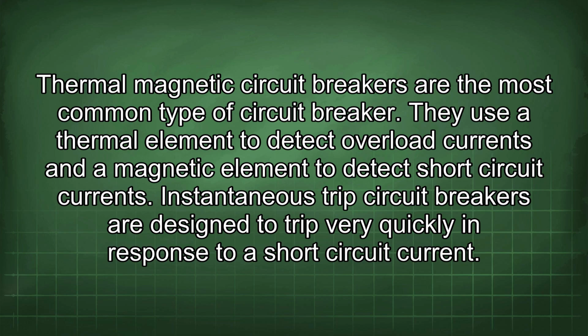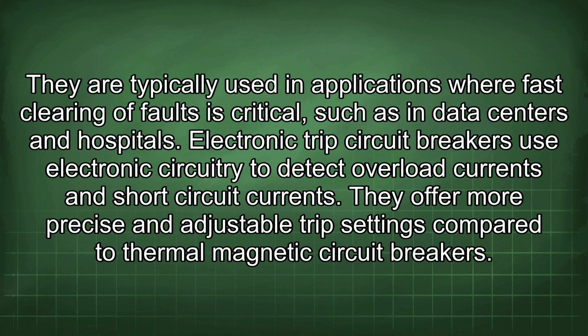Instantaneous trip circuit breakers are designed to trip very quickly in response to a short-circuit current. They are typically used in applications where fast clearing of faults is critical, such as in data centers and hospitals. Electronic trip circuit breakers use electronic circuitry to detect overload currents and short-circuit currents. They offer more precise and adjustable trip settings compared to thermal-magnetic circuit breakers.